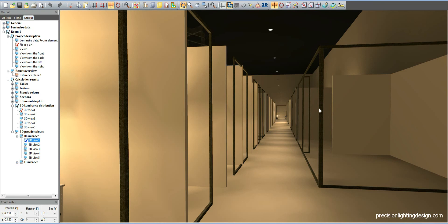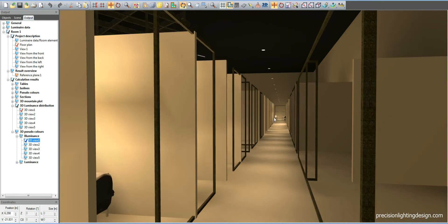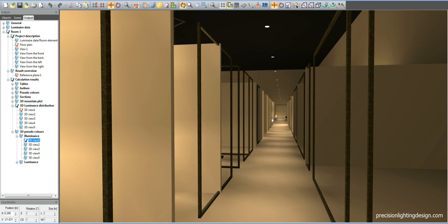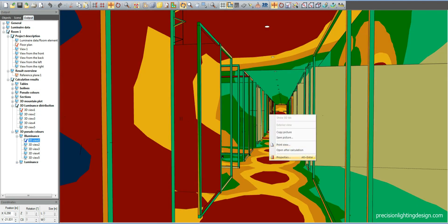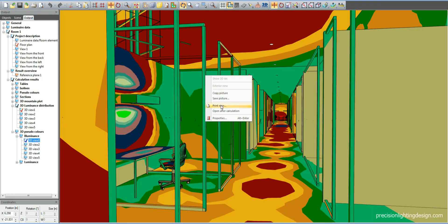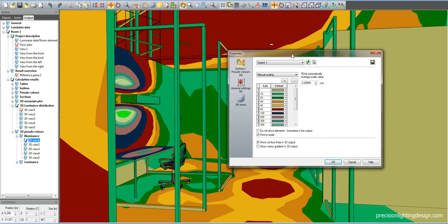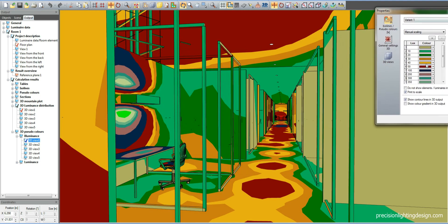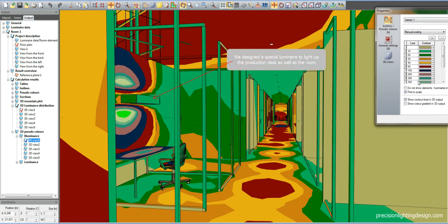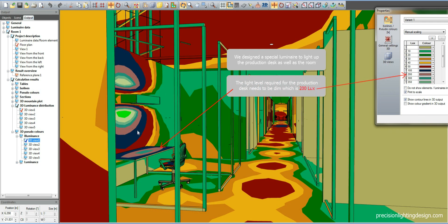We just entered the offices located in the back side of the architecture. Please observe carefully at the office located on the left hand side. A special luminaire is designed to light up the production desk as well as the room itself. The light level required for the production desk needs to be dim, which is 200 lux.